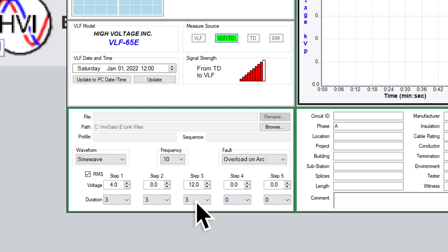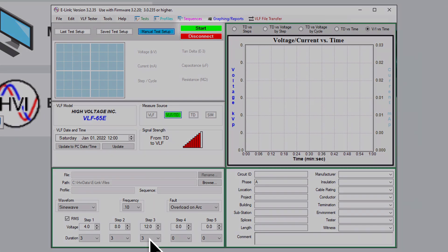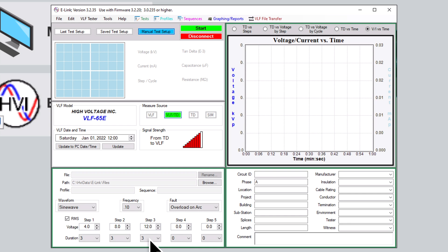Make sure the Tan-Delta bridge, VLF-E series HiPot, and cable shielding are all connected to ground. Follow all local safety practices and precautions when working with medium to high voltages. Once you are sure you are properly set for a Tan-Delta test, you can start the test remotely from the e-link software, or directly from the front panel of the HiPot.